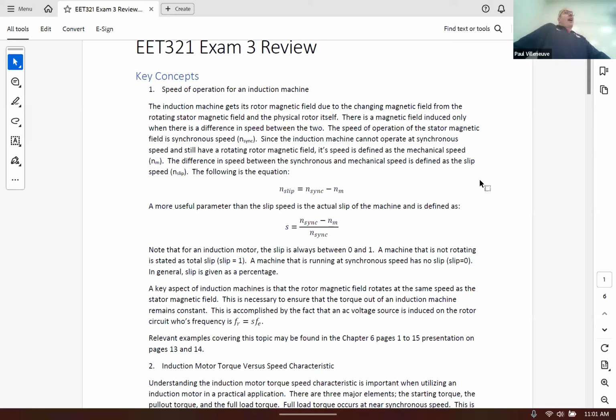On the rotor, because you have three-phase windings on the rotor, and they're short-circuited, you can have current flow through there. And that current flow does exist because you have magnetic fields that are changing. The changing magnetic fields come from the rotation at synchronous speed, plus the actual physical rotation of the shaft, essentially, or the rotor. And the rotor can't operate at synchronous speed, because if those two are operating at synchronous speed, there'd be no changing magnetic field, right? You have a hunk of wire spinning at the same speed as the synchronous speed, so there's no changing magnetic field. So there always has to be a delta.